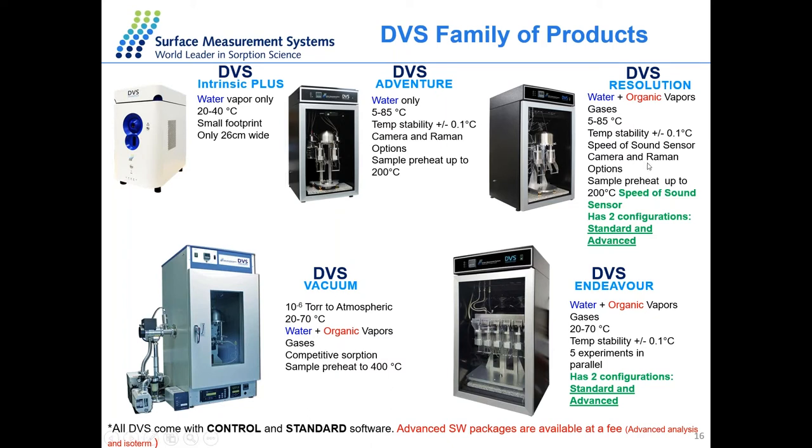The DVS Resolution also has a speed of sound sensor configured in the system when using organic vapors. DVS Endeavour uses water and organic vapors as well as gases, and has five chambers so we can measure five different samples simultaneously — very useful if you have samples you wish to run with one method all at the same time. We also have a DVS Vacuum, which can present samples under vacuum conditions using water and organic vapors, and allows preheating the sample up to 400 degrees, whereas other instruments can preheat up to 200 degrees.